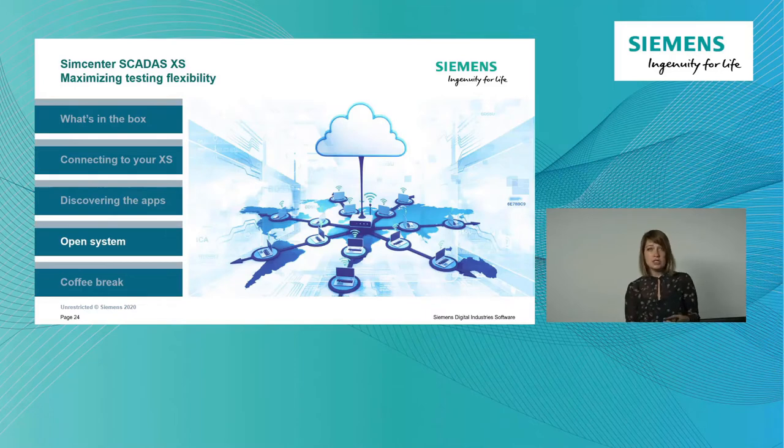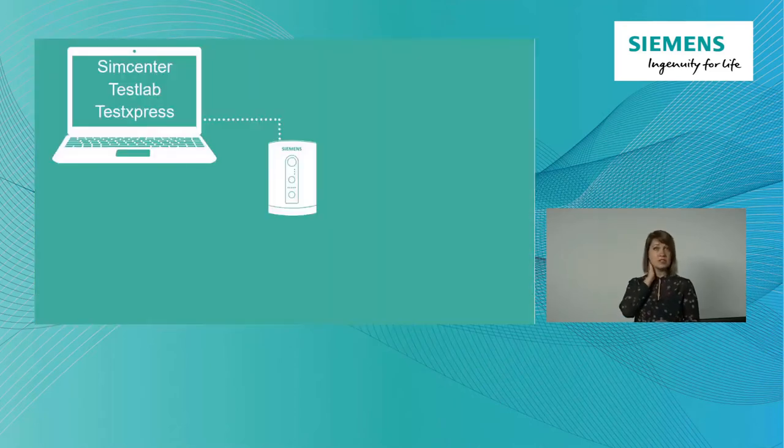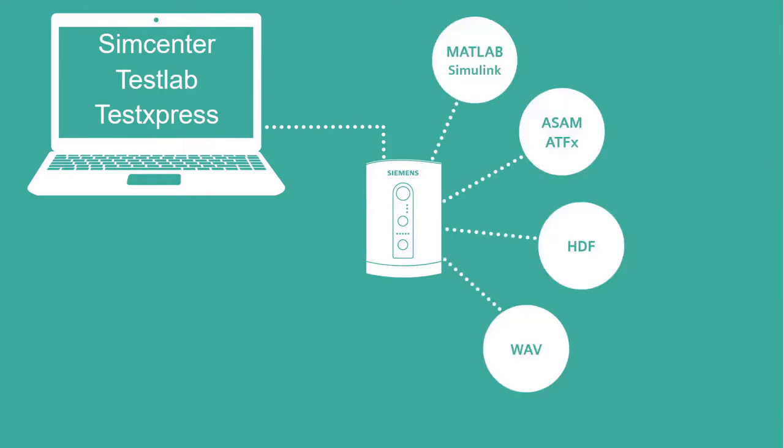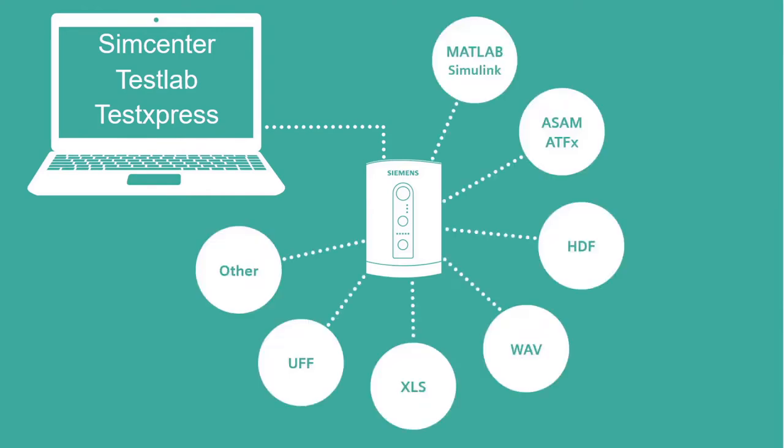Of course not everyone has to use TestLab or TestXpress - we would love that, but another strong point of the SimCenter XS solution is that it is a very open system. If you have a SCADAS XS, you can of course work with TestLab and TestXpress, but you also get a Data Recorder Conversion Tool. This tool allows you to export your measured data into any of the formats shown on screen - absolutely free, no license required. You can export to MATLAB, ASAM, ATFX, HDF, WAV, Excel, Universal Files, and many others, to work with your data on any platform you want.